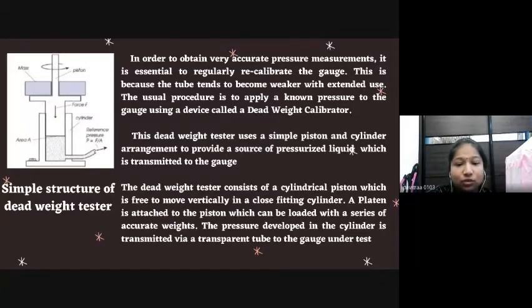Since the true pressure of the liquid can be easily calculated, the value can be compared directly to the reading on the gauge over the complete scale range. The dead weight tester consists of a cylinder piston which is freely moved vertically in a close-fitting cylinder. A flat platen is attached to the piston which can be loaded with a series of accurate weights. The pressure developed in the cylinder is transmitted via a transparent tube to the gauge under test.